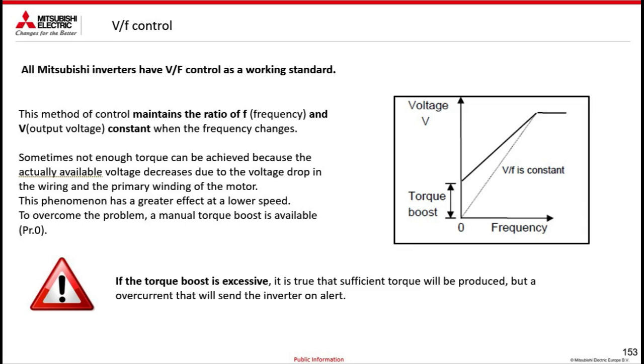So at least I can avoid this classic problem of a standard graph of an asynchronous motor, but you have to be careful because this parameter may bring some problems. If you use it the right way, you will be able to obtain higher torque values, and therefore it's fine. If, however, you push too much with this torque boost, given the classic Ohm's law, you will have a really high current rise, and therefore you will have to deal with other problems, like a current error. So use it with caution. The set value is from 0 to 30%.